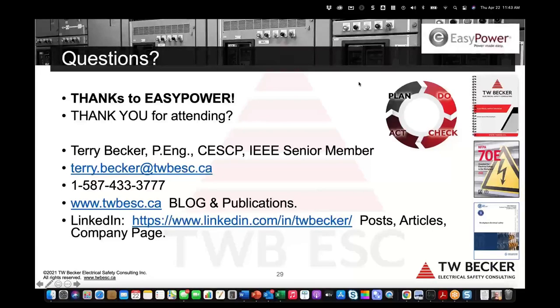That was originally identified by Dr. Ralph Lee, who I'm proud to say is an Edmonton, Alberta PhD electrical engineer who, in the late 1980s and early 1990s, first did research and empirical calculations to define incident energy at a distance and the arc blast pressure. If you look to his papers and the old Yellow Book, which is now the IEEE 3007.1, 2, and 3 documents, his graph shows up there, and it shows that blast pressure correlates to arcing fault current and has no direct correlation to incident energy. So 40 cals is not dangerous.